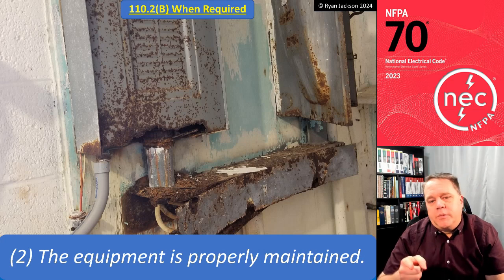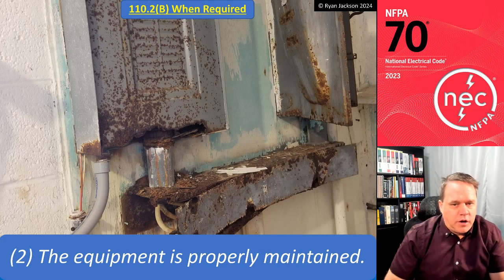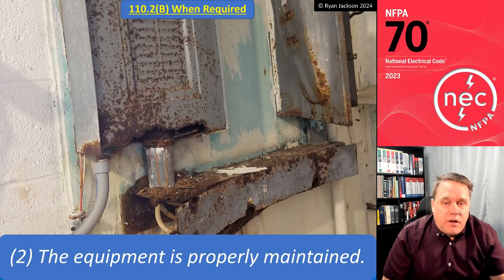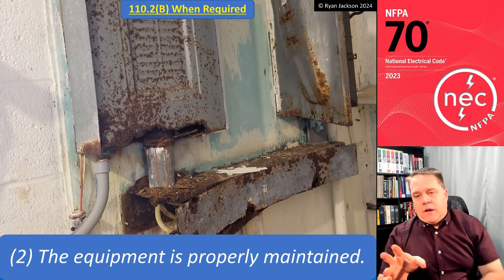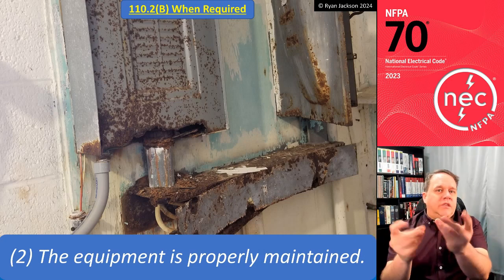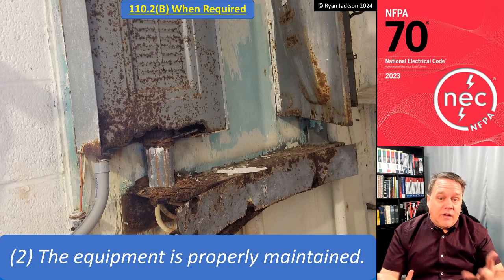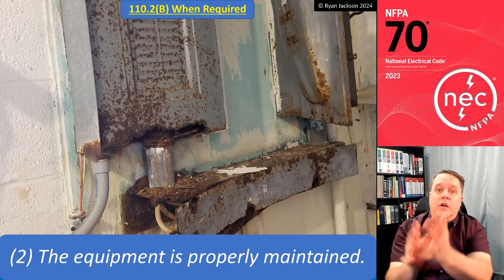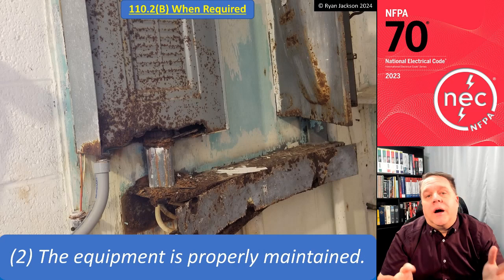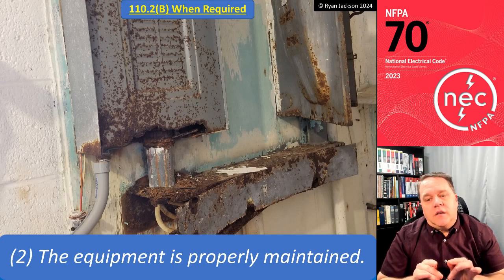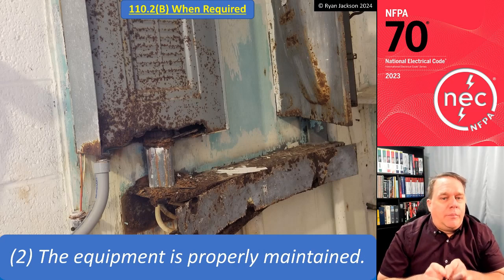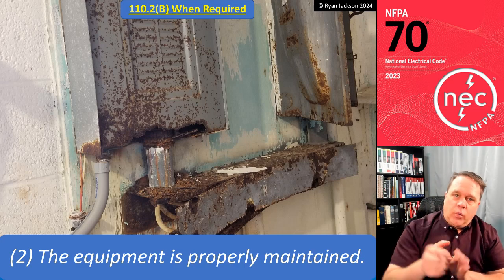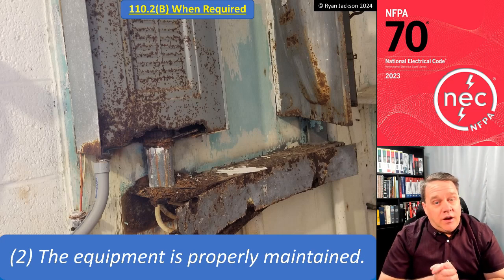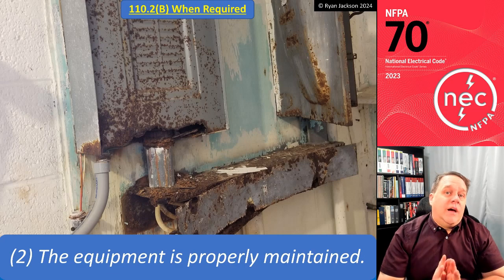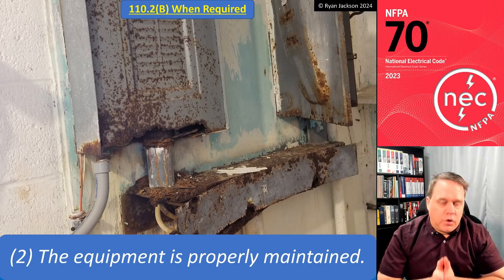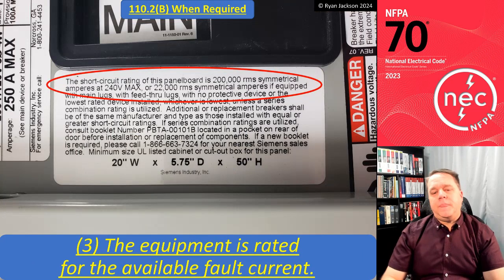So can I go up to this thing and start flipping circuit breakers on? Absolutely not. We have no idea if there's loose metal parts in there, right? If the inside has rust and it's got parts that are ready to fall down. No, there is no normal operation of this equipment because this is not in a normal operating condition. If I needed to work on that panel board, I would need to what? I would need to shut it off. I would need to establish an electrically safe work condition.